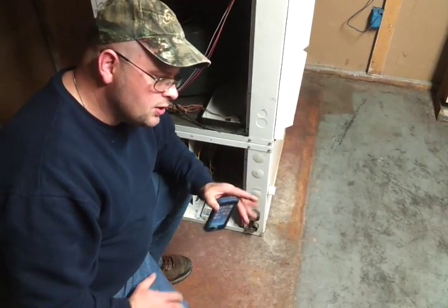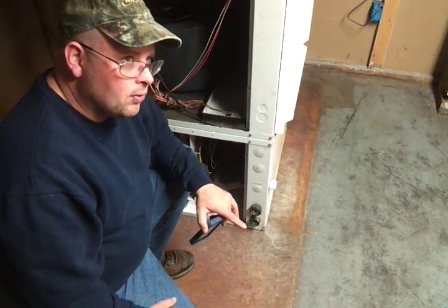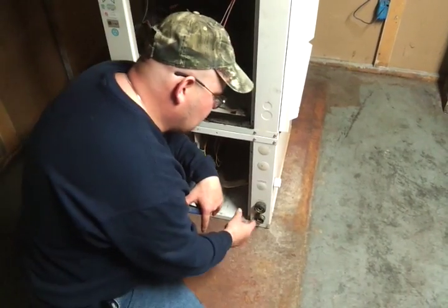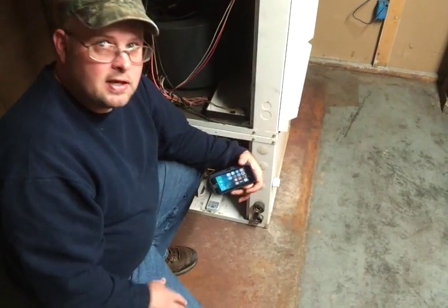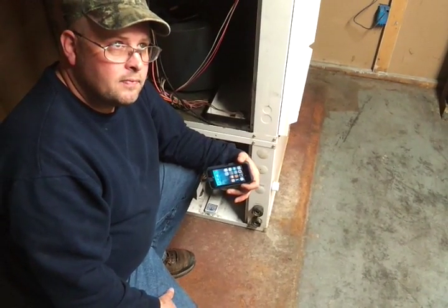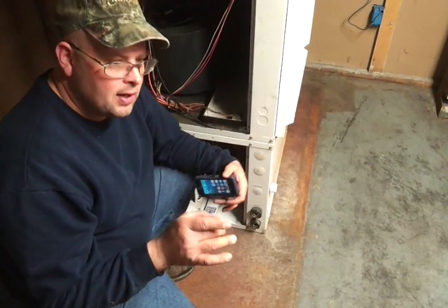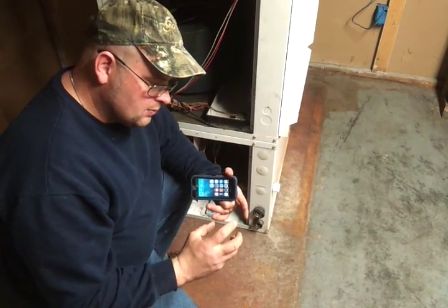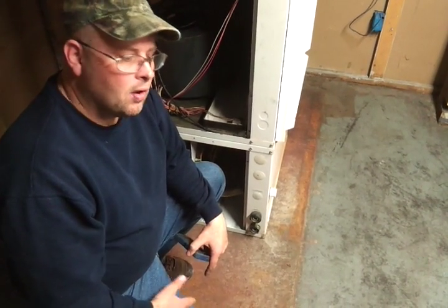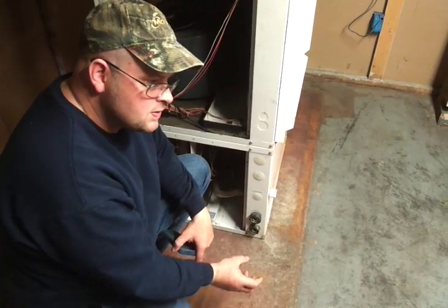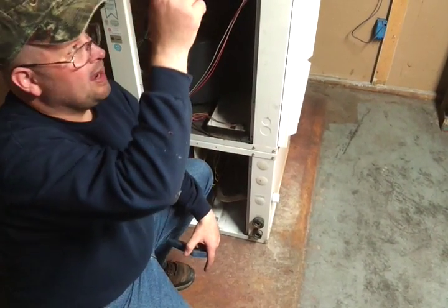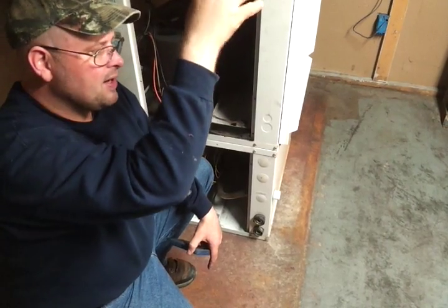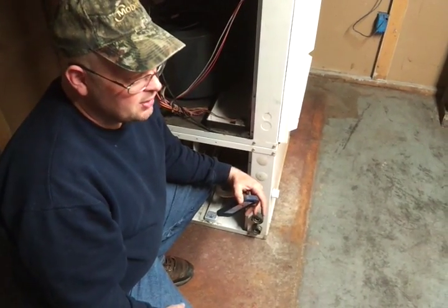Okay, so here's what you should do. You should take a nipple, like a brass nipple of some sort, thread that in there, and then you can thread your PVC onto that. Okay? We're actually going to run some 1-inch PEX. Do not run a brass fitting and then crimp a PEX fitting on there. Because if it overheats, it will melt that PEX like it's butter. So it'd be a good idea to go from the unit, brass, to PVC, and then you'd go like 2 or 3 feet down, then the 1-inch PEX you guys were using. You'd be fine with that.